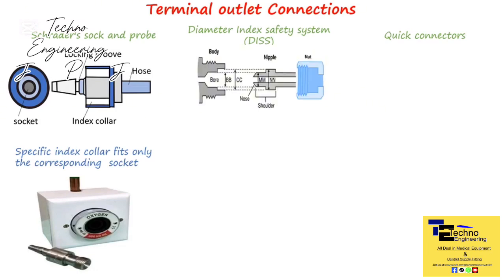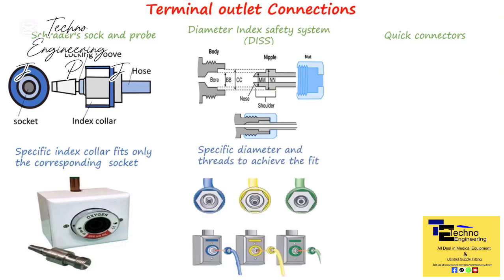The diameter index safety system was developed as a standard for medical gas lines under 200 psi pressure. It is used to connect anesthesia machine hoses to terminal units. This system consists of a body, nipple, and nut combination. Two concentric bores, BB and CC shown in the diagram, on the body fit into two shoulders, MM and NN, on the nipple. Only when these parts align can the threads of the nut and body engage securely.